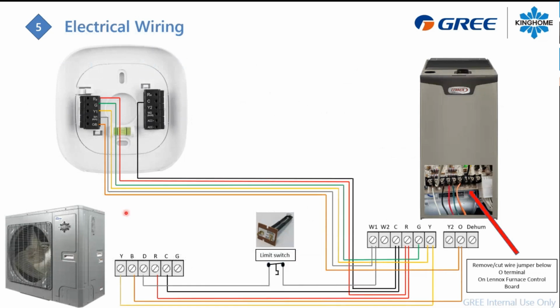I built this kind of diagram to use as a reference. In that case, we use an Ecobee thermostat. From the thermostat, you will use RC when talking about Ecobee. You won't use RH. I know the new kind of thermostat from Ecobee only uses the R. There's no more RC, RH. You just have one R. But in the case that you have both, well, you need to use the RC. So from your thermostat, the minimum wire you need is a 6 wire coming from the thermostat.